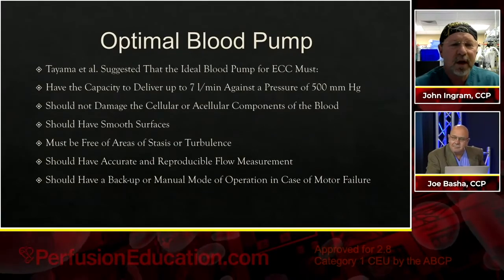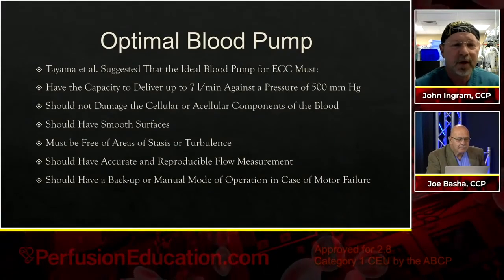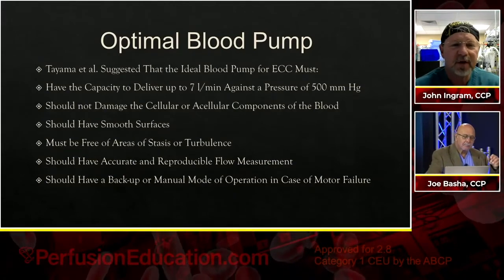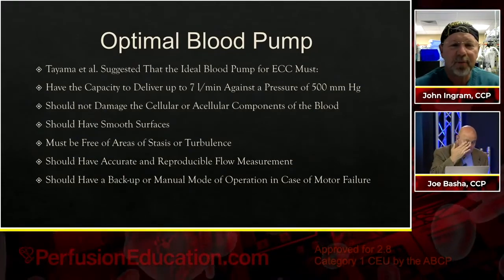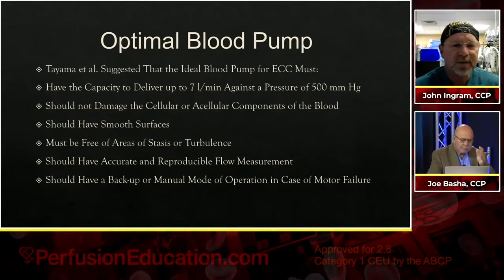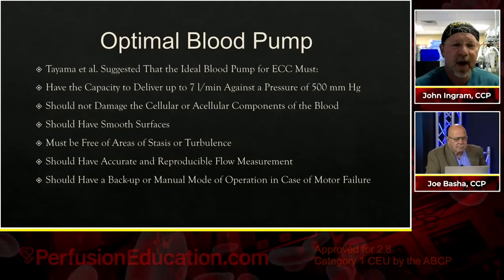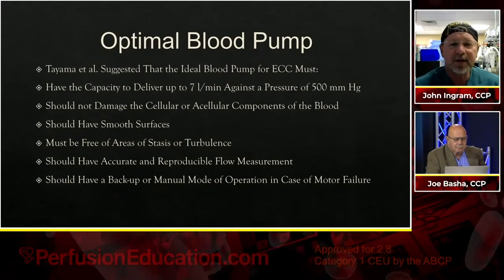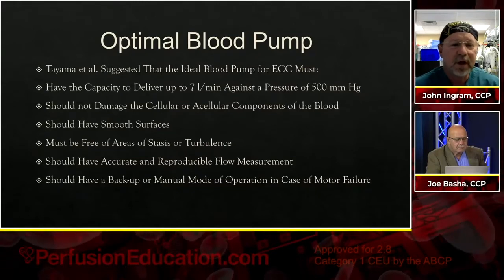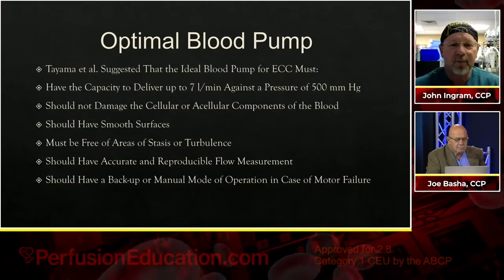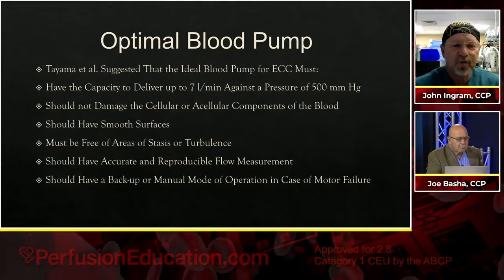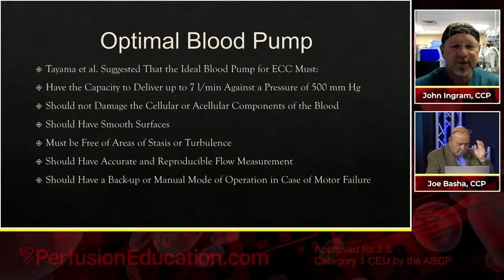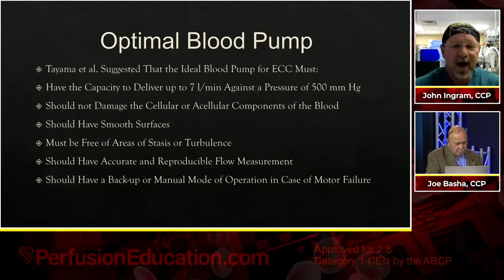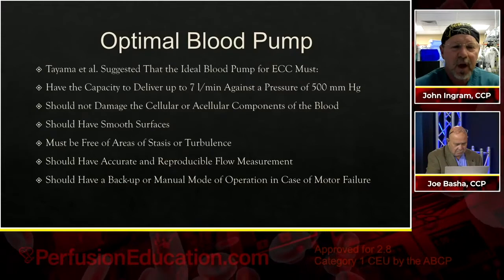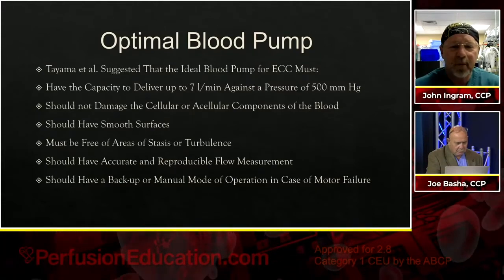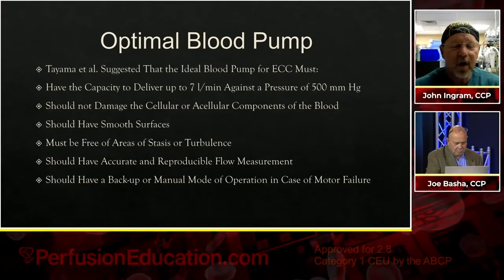And so what would be the optimal blood pump? Dr. Tayama, about 10 years ago, suggested that the ideal blood pump for extracorporeal circulation must have the following features. It must have the capacity to deliver up to 7 liters a minute against a pressure of 500 millimeters of mercury. It should not damage the cellular or acellular components of the blood. It should have smooth surfaces. It must be free of areas of stasis or turbulence. It should have accurate and reproducible flow measurement. And you should have a backup or manual mode of operation in case of catastrophic failure of the pump.